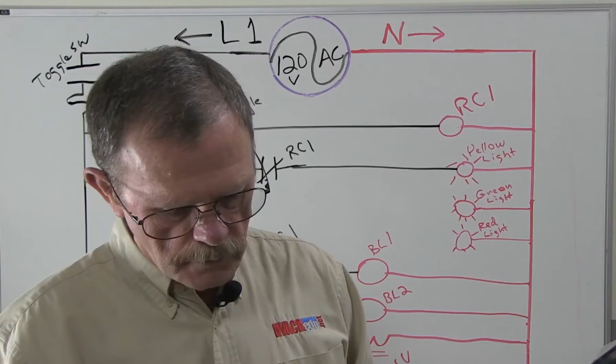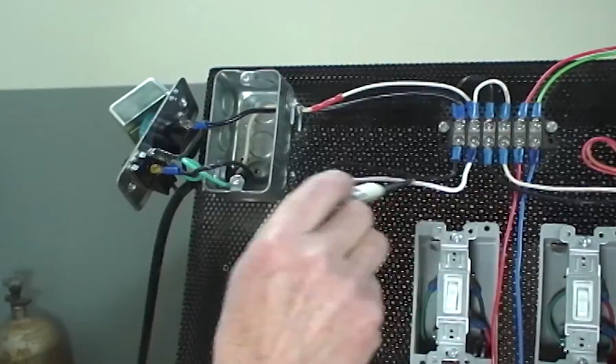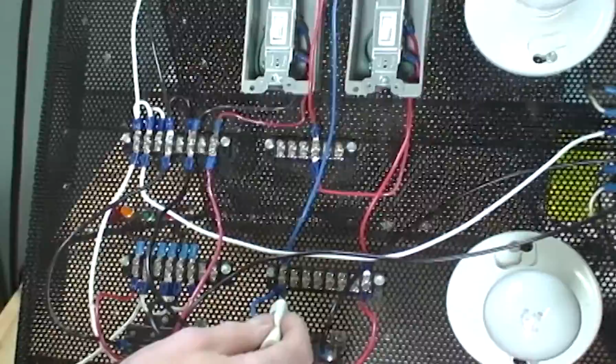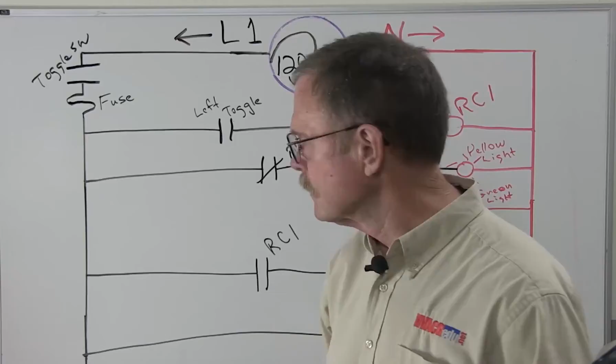Let's do the 24 volt circuit. And here's the power, 24 volt, red and green, comes in here to this terminal strip up here. All right, the blue wire, one side of the 24-volt circuit, goes all the way down, hits this terminal strip, boom, goes to one side of the relay coil. Okay? So, and we'll just call that this side of the circuit.